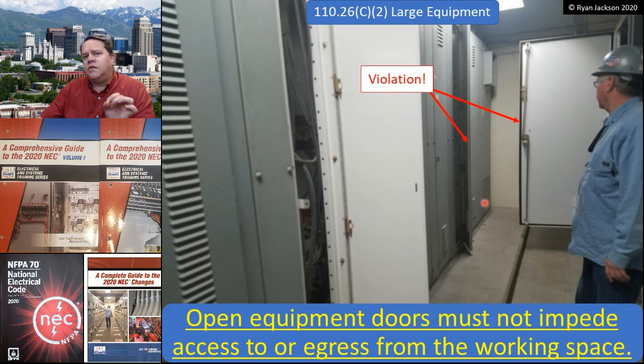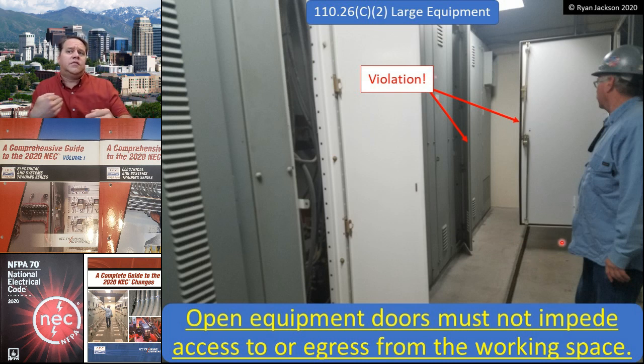Now, one of the things that's incredibly difficult with this section is it doesn't give us a value. It can't impede access to less than 24 inches of width or anything like that. It simply says open doors must not obstruct your egress. So if you wanted to take a literal approach to this requirement, you could never comply with it in any installation as currently written, because any open door by definition impedes your egress.